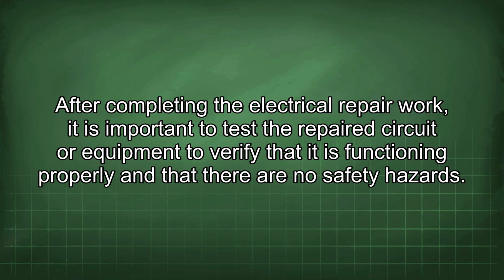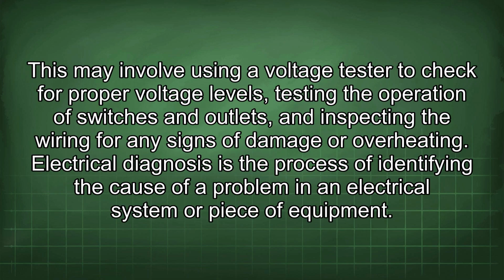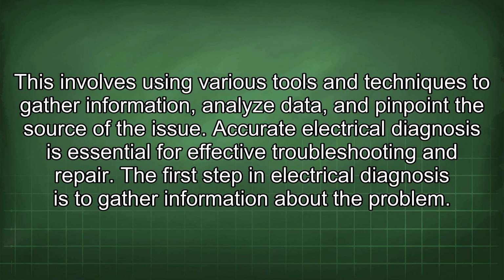After completing the electrical repair work, it is important to test the repaired circuit or equipment to verify that it is functioning properly and that there are no safety hazards. This may involve using a voltage tester to check for proper voltage levels, testing the operation of switches and outlets, and inspecting the wiring for any signs of damage or overheating. Electrical diagnosis is the process of identifying the cause of a problem in an electrical system or piece of equipment. This involves using various tools and techniques to gather information, analyze data, and pinpoint the source of the issue. Accurate electrical diagnosis is essential for effective troubleshooting and repair.